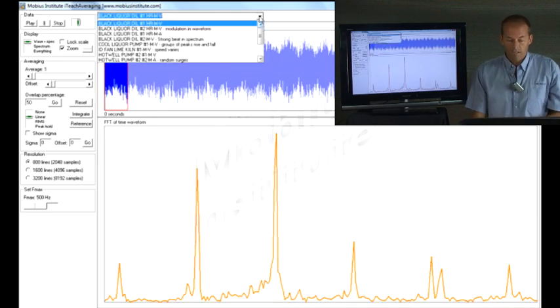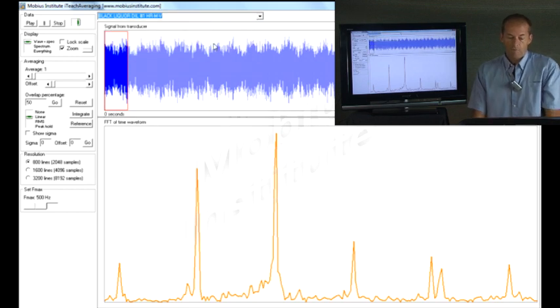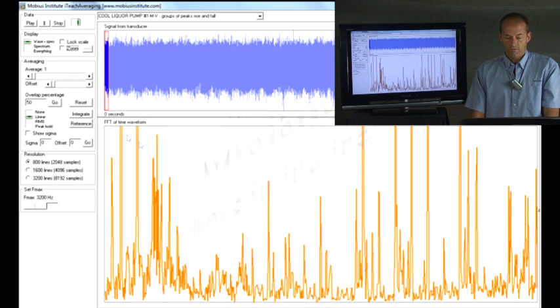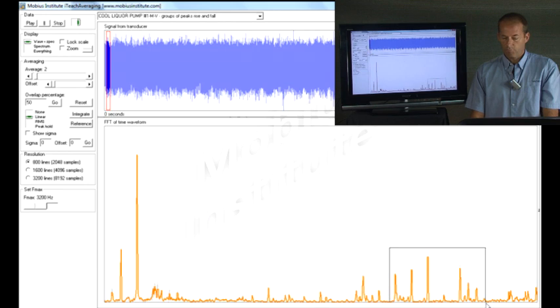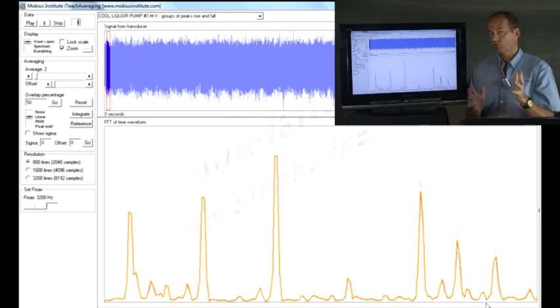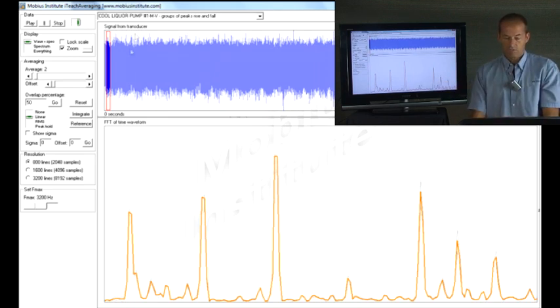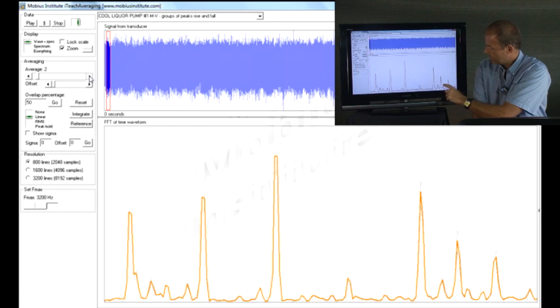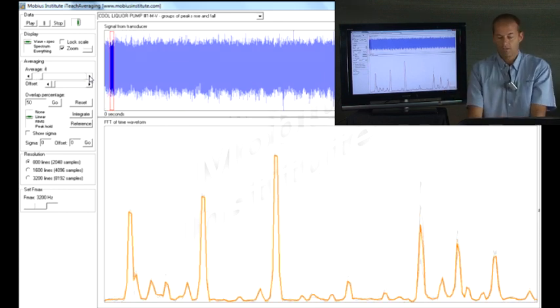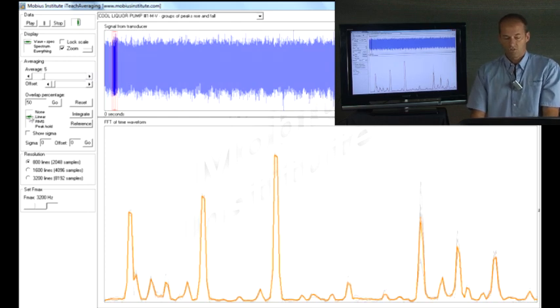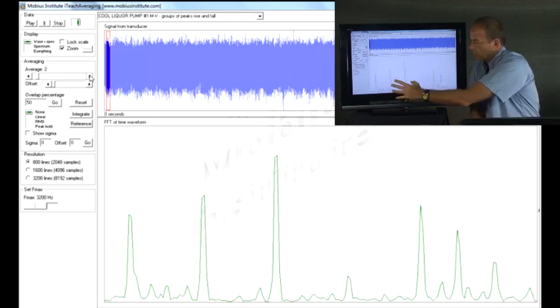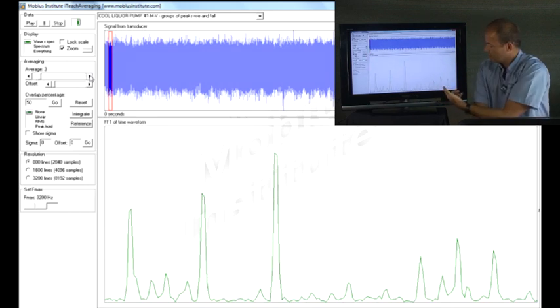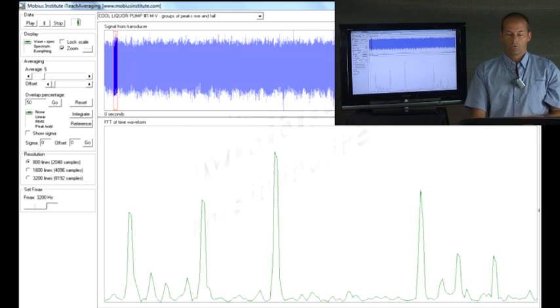Another sample of vibration may just have certain areas where there is vibration of interest. Just reset that, there we go. If I zoom in here for example we'll see that there's some vibration that's very constant in amplitude all the time, another vibration that varies much more. So if you watch just in this area here you can see these, you'll see the gray peak in the background, how much variation there is. In fact if I just turn off the averaging for a second we just watch the live data, you see again that the instantaneous spectrum, the green one, isn't changing much in this area and changing a lot over here. Now really this is just an ordinary machine.